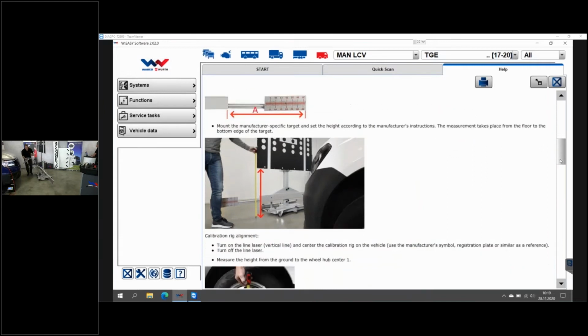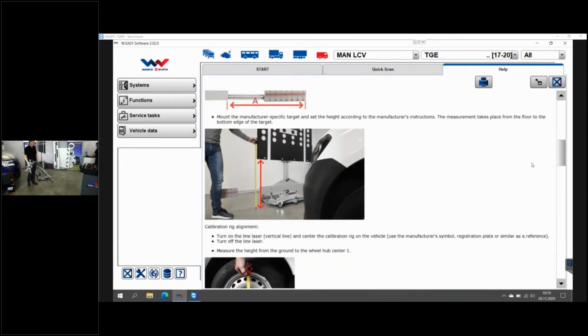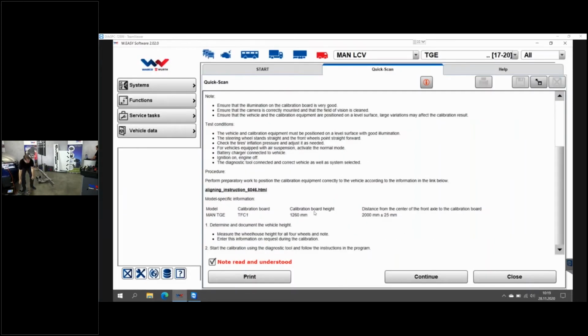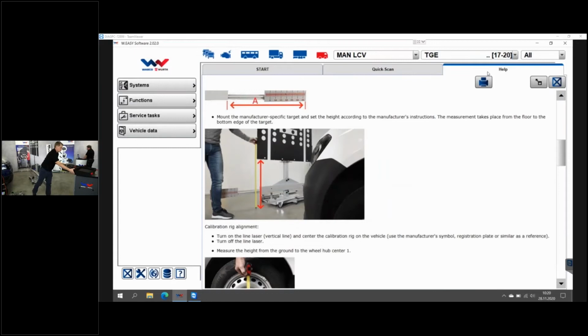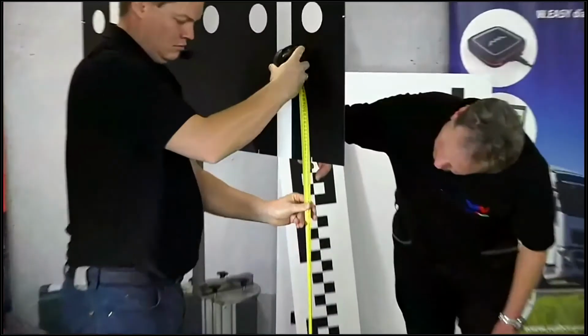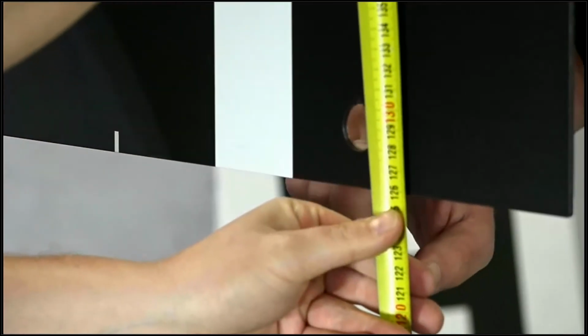Next topic, we have the mounted target already. We have to set up the proper height. Where do I get the height? As I explained before, down here, calibration board height, 1260 millimeters, from floor to the under level of the target. So we have a measure tape in here. 1260 millimeters. We have the proper size.